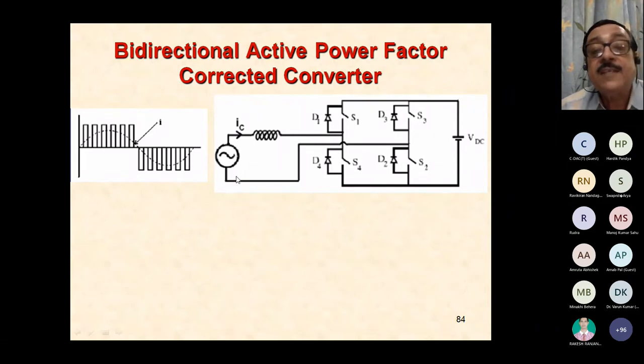And this waveform is a sine wave. So even when this waveform has a zero magnitude here, there is a finite magnitude of voltage existing. So if the inductor is not there, there will be a direct short circuit and a heavy current flow between the two. So the inductor serves as the harmonic current limiting reactor or current limiting reactor for this structure. And it has a dual function. And this is the way the bidirectional active power converter operates.